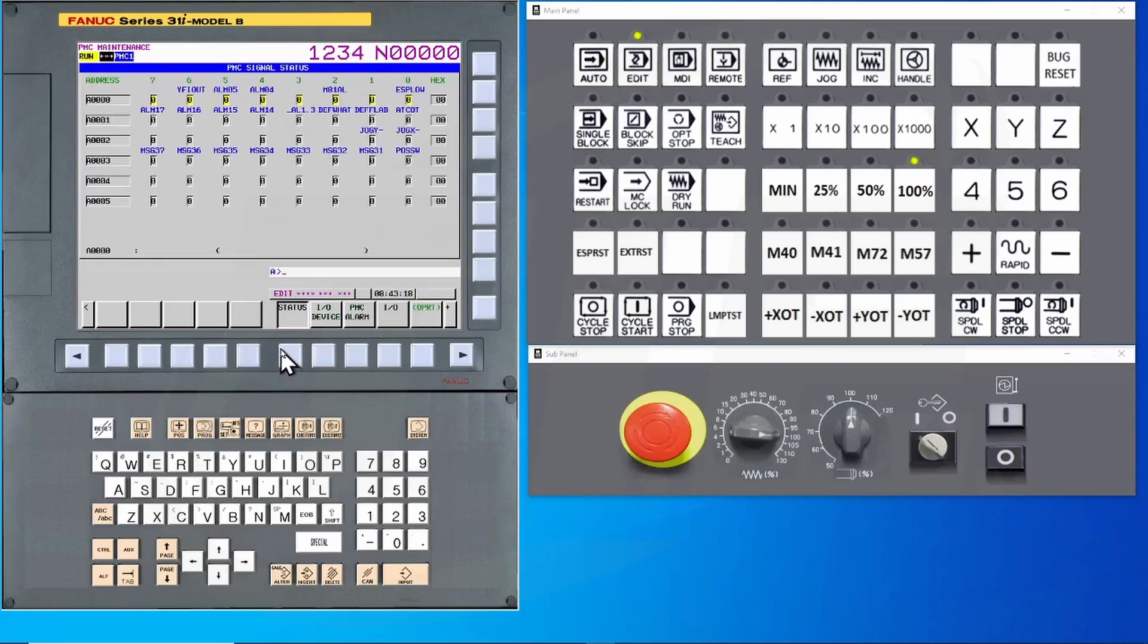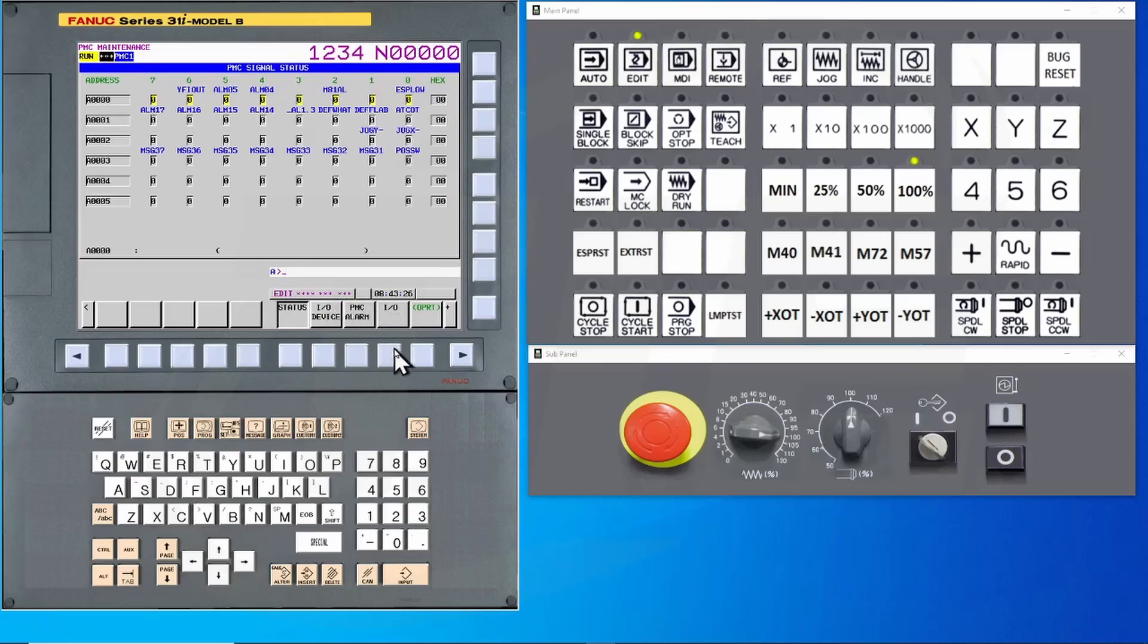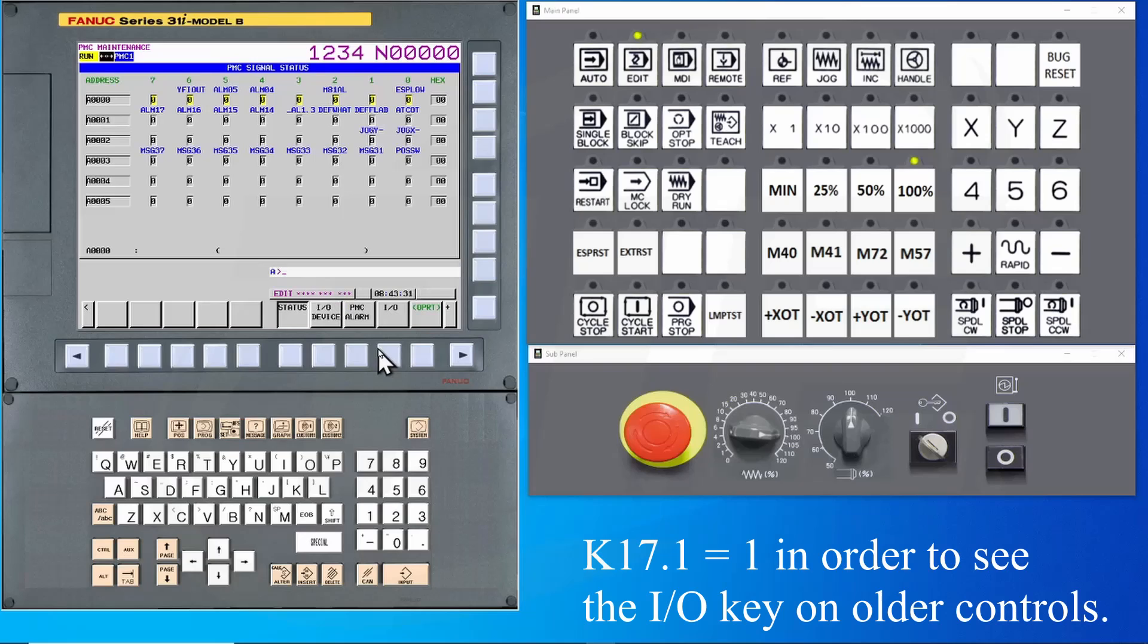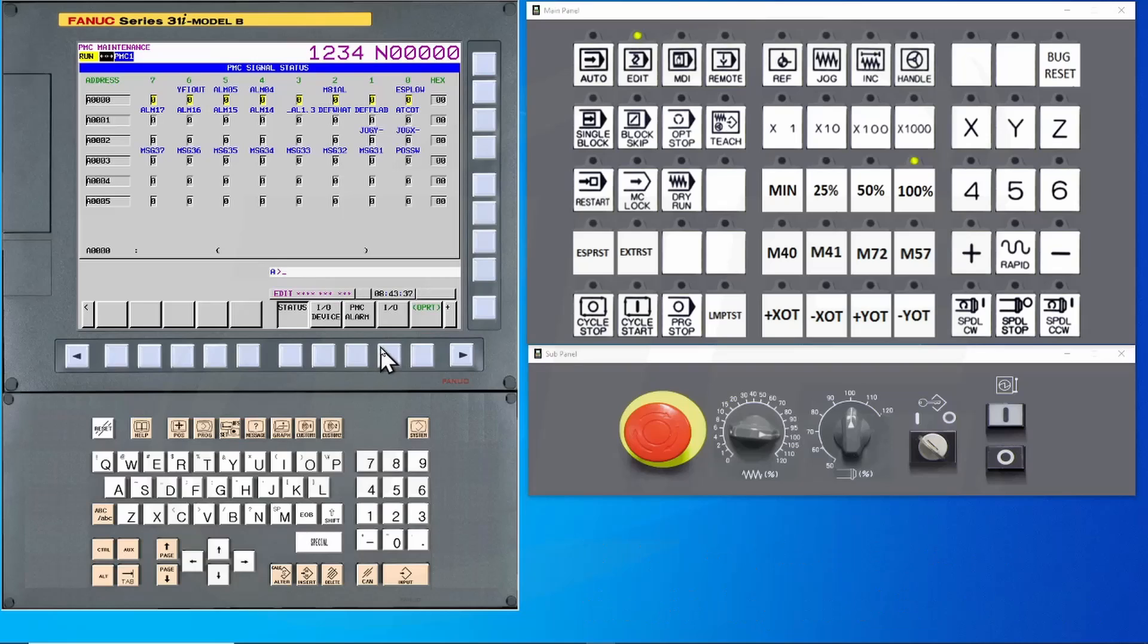If need be, press the Continue button until I/O is displayed. Do not confuse this with I/O device. As a side note, on older model controls, it was necessary to turn on System Keep Relay K17-bit1 in order to see the I/O soft key. Now press the I/O soft key.